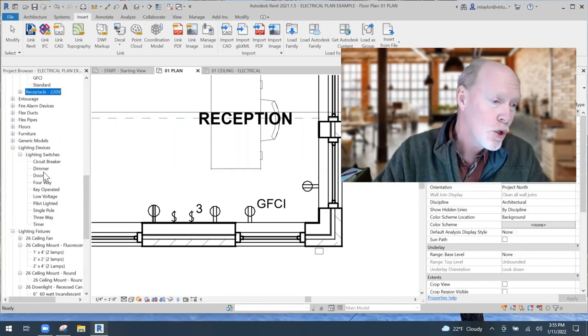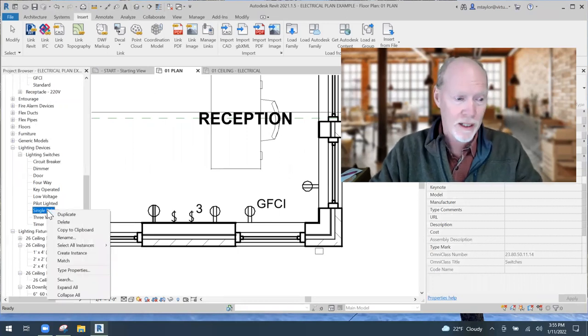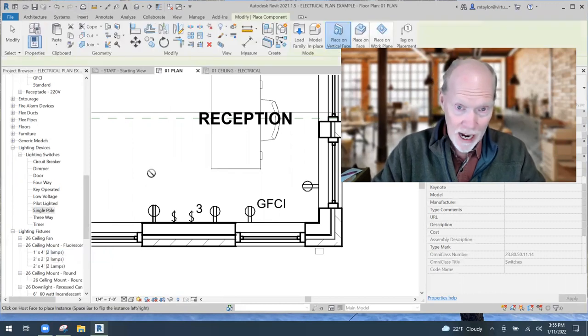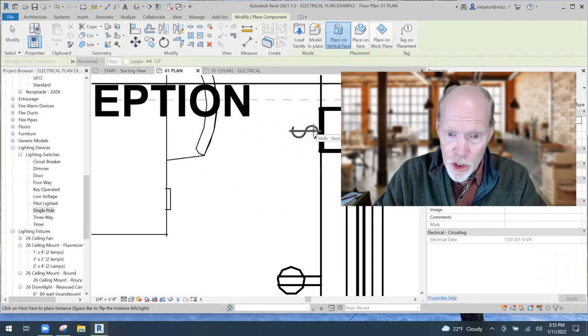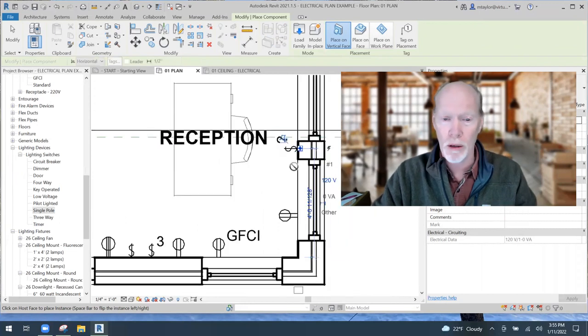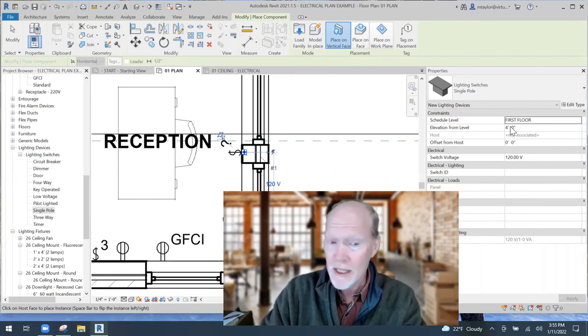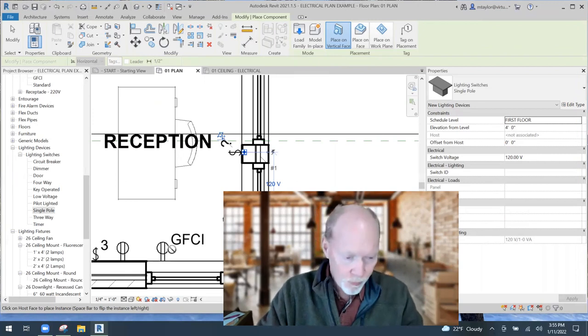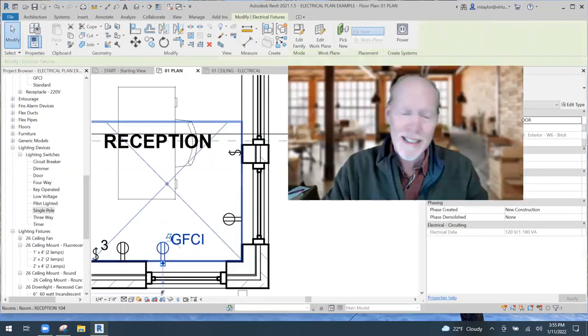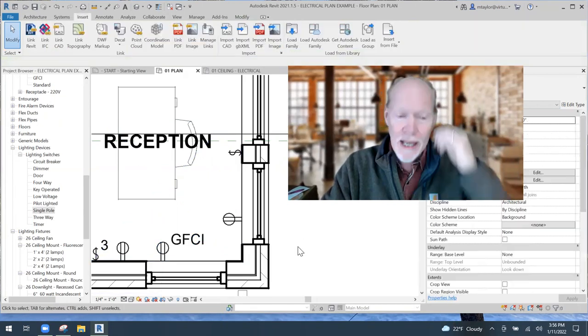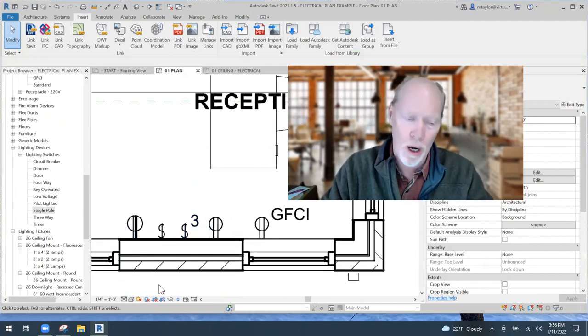To place a switch, click on Single Pole, right-click it, and choose Create Instance. Make sure it's set to be placed on a vertical surface — that's listed at the top of the screen. Then zoom in and put the switch on your wall. Switches typically come in around four feet elevation from the level. Outlets will come in low to the floor, around one foot six, and you can set those heights to whatever you want.